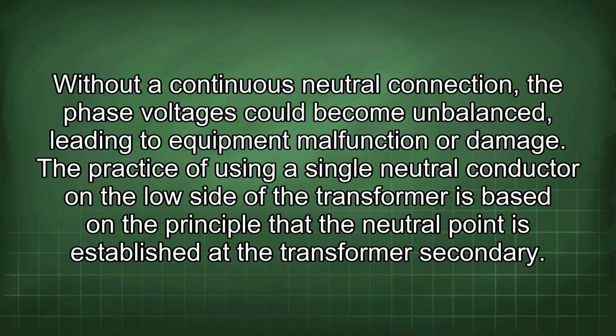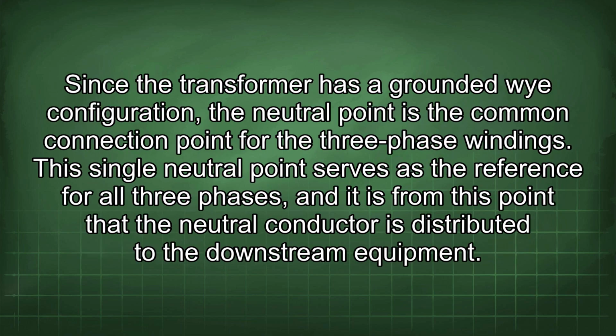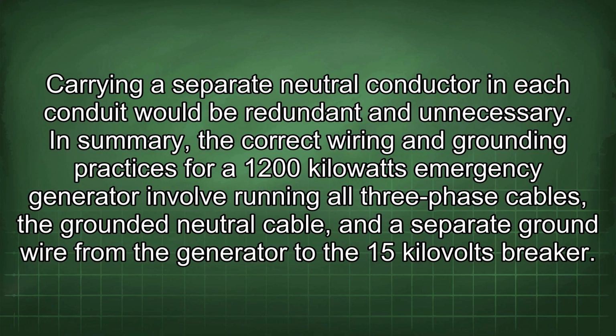The practice of using a single neutral conductor on the low side of the transformer is based on the principle that the neutral point is established at the transformer secondary. Since the transformer has a grounded Y configuration, the neutral point is the common connection point for the 3-phase windings. This single neutral point serves as the reference for all 3 phases, and it is from this point that the neutral conductor is distributed to the downstream equipment. Carrying a separate neutral conductor in each conduit would be redundant and unnecessary.